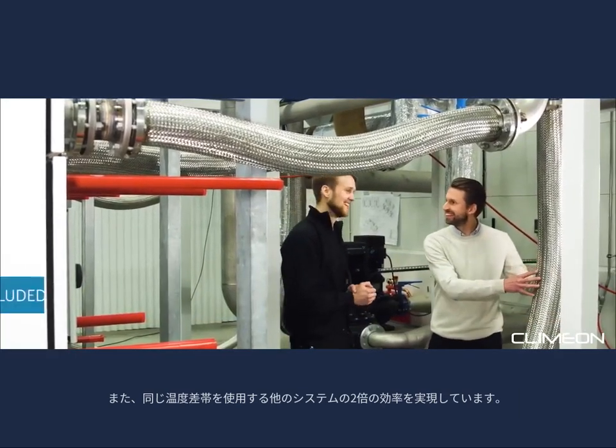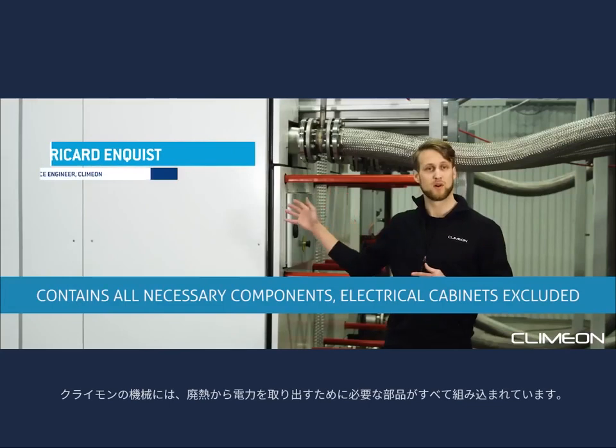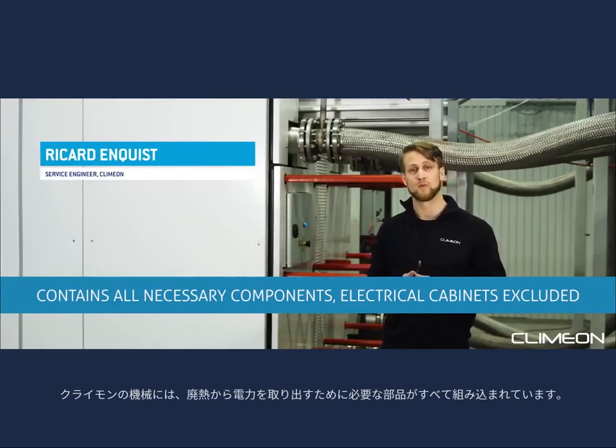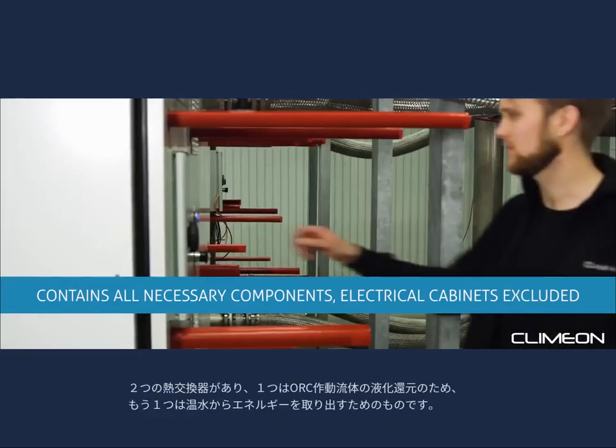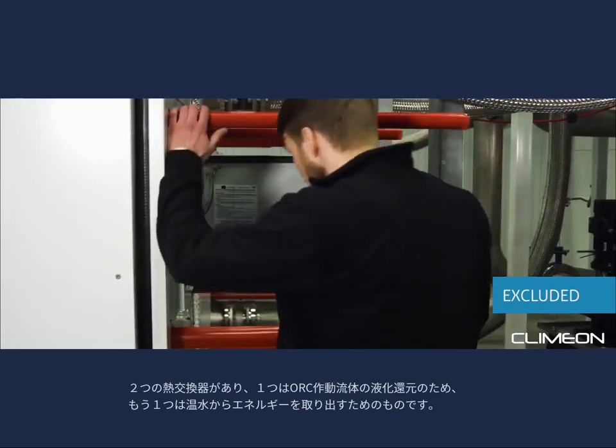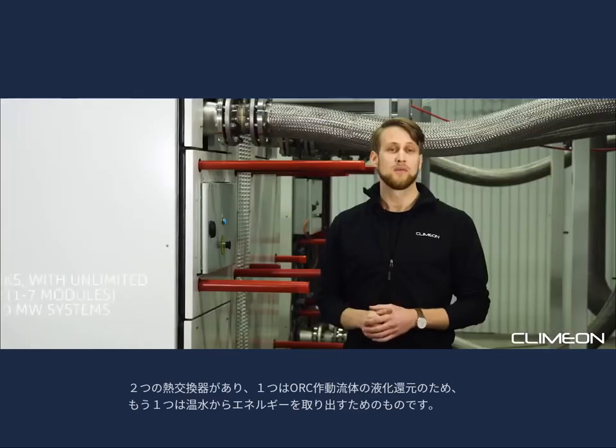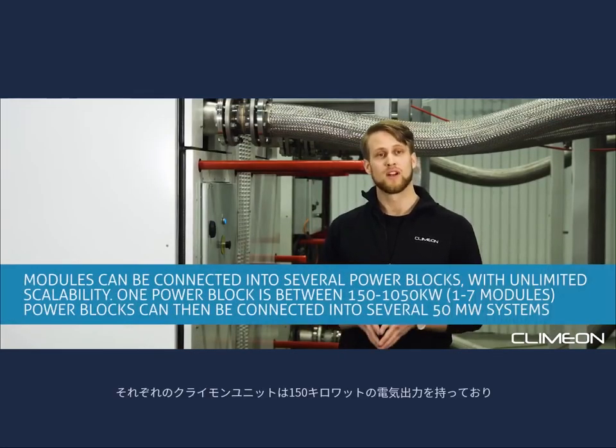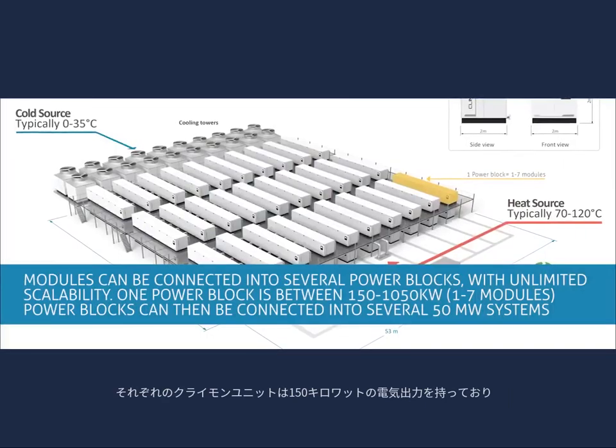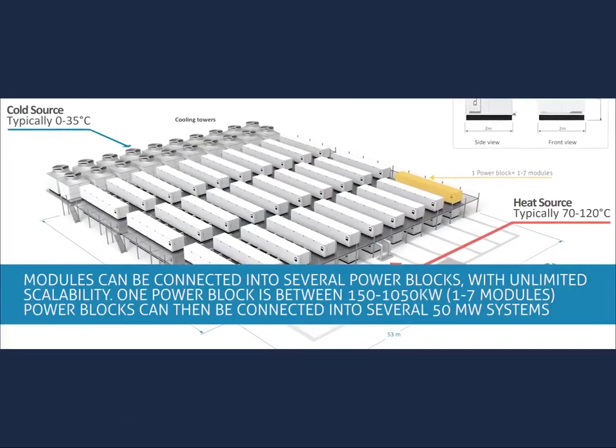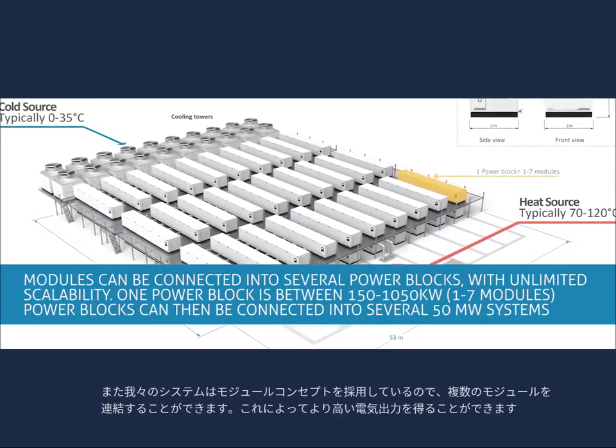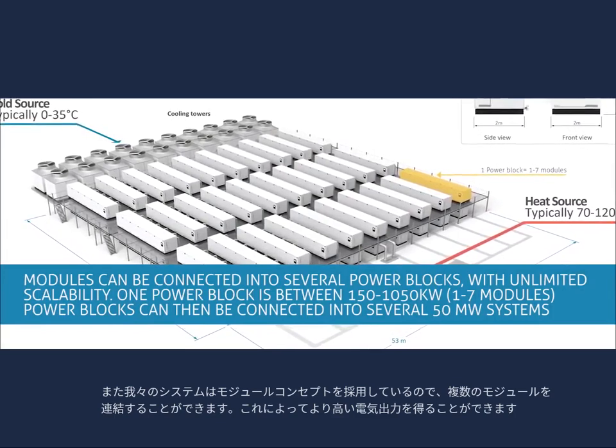temperature intervals. The Climeon machine contains all components needed to extract electricity from waste heat. The heat exchanger for condensation and to extract the energy from hot water. Each Climeon unit has an electrical output of 150 kilowatts, and we have a modular concept so you can stack several modules next to each other to get a higher electricity output.